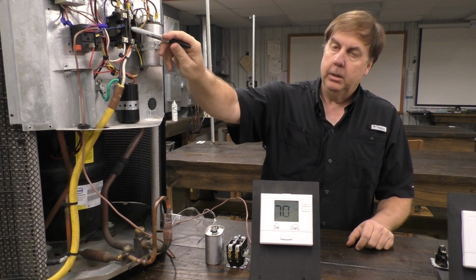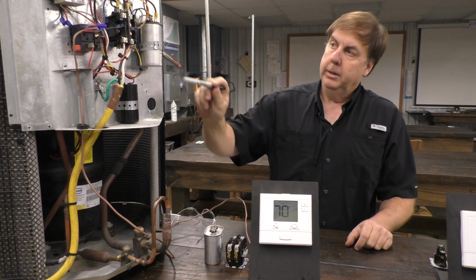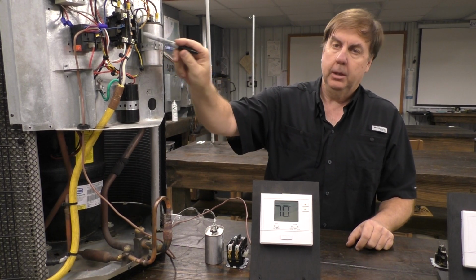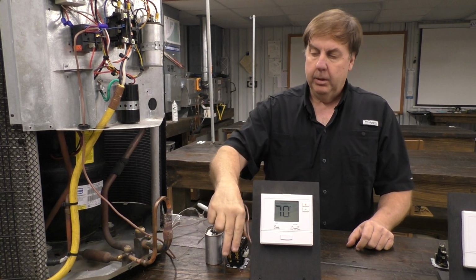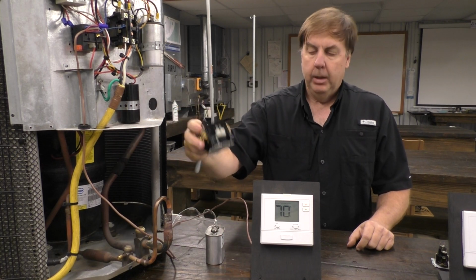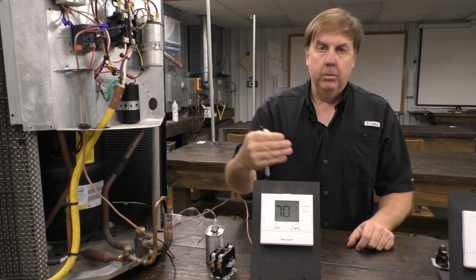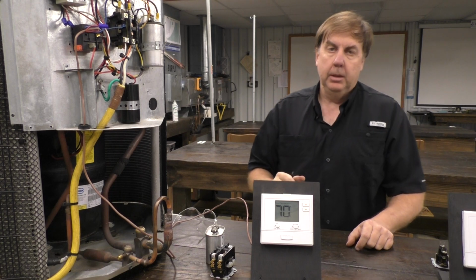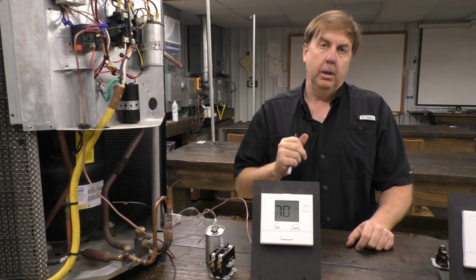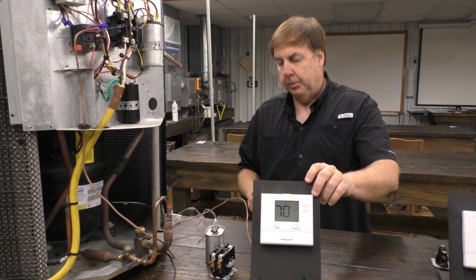Because when it pulls in, everything runs. So now I simply need to check voltage here at the contactor. If I have it, I just need a new contactor. If I don't have it, I'll start going backwards to see what the problem is. It could just be that float switch we talked about earlier—it could be something that simple.